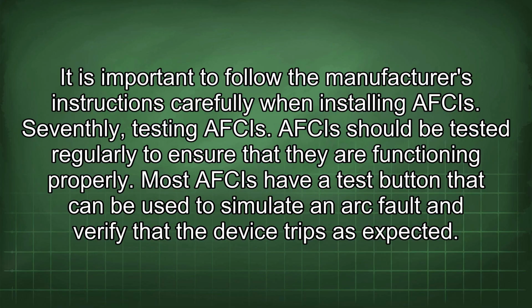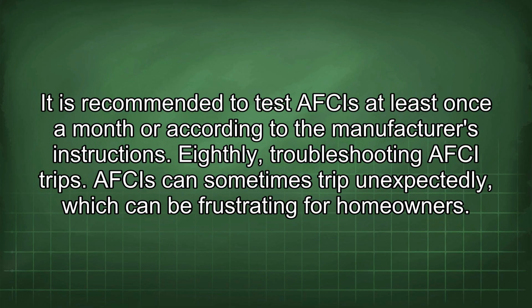Seventhly, testing AFCIs. AFCIs should be tested regularly to ensure that they are functioning properly. Most AFCIs have a test button that can be used to simulate an arc fault and verify that the device trips as expected. It is recommended to test AFCIs at least once a month or according to the manufacturer's instructions.